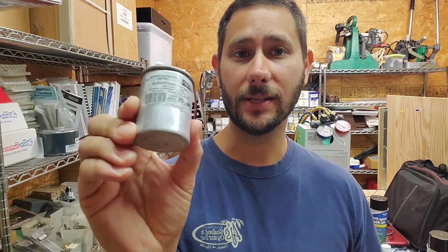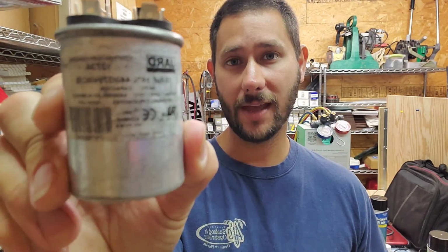So let's move on. You have a forced draft air conditioning system usually, and the air passes across the evaporator, and you have a blower motor that accomplishes that air movement. So if your airflow from your blower motor is not proper, then that can cause your unit to freeze up. So making sure that your evaporator fan motor or your indoor fan motor is operating correctly is a good thing to check. You need to make sure that not only your capacitor for your indoor fan is good, that way it's running at the speed it needs to, but also your fan relay.